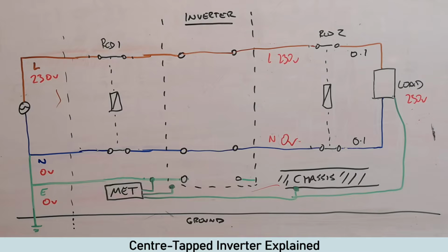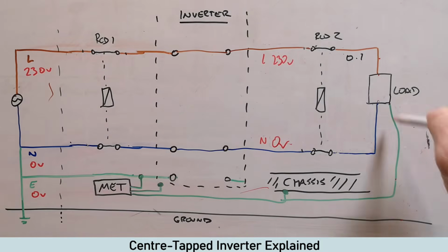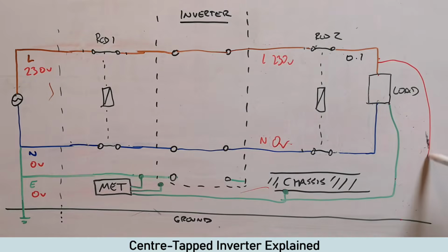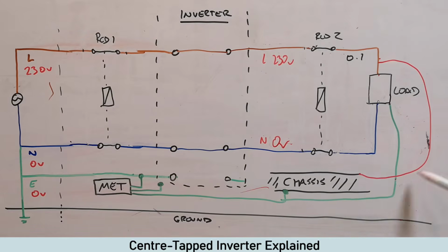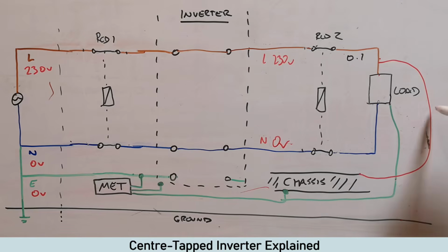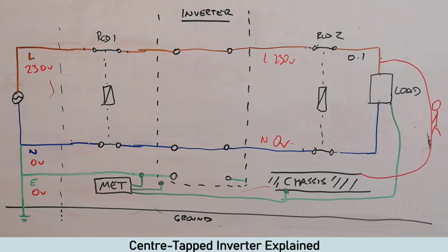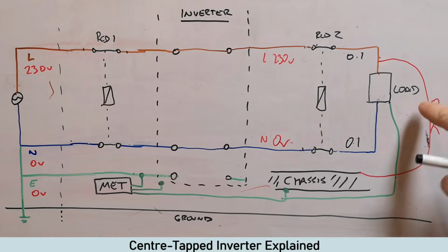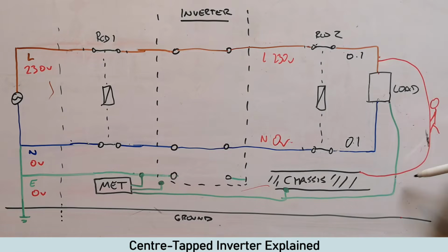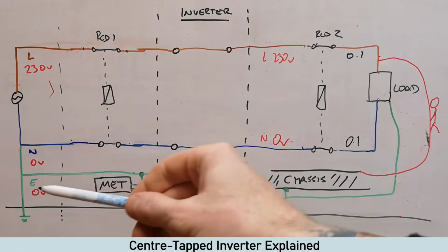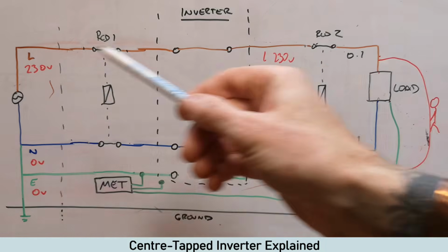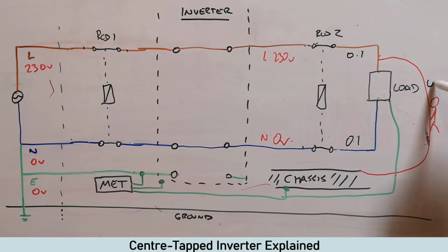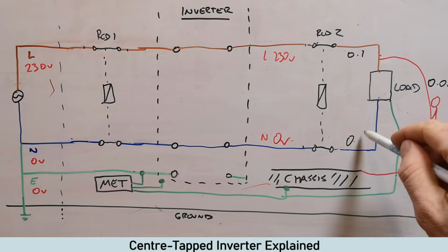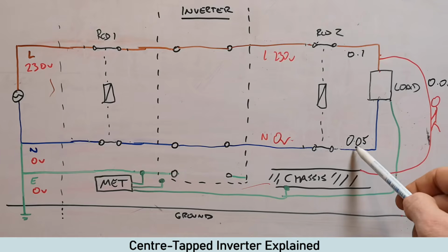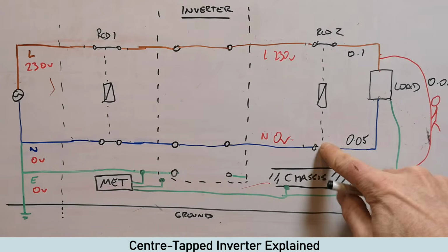Now if there's a fault, you come along and you're touching this live here, and let's just link it. Let's say you stood on the chassis and then you're touching that live there. So this is you touching that. Now again, the RCD wants to see 0.1 coming back in, but because you're touching it, some of that is going to flow through you like we did before, then through the chassis, back through here, through this neutral to earth bond, and back up again. So you're part of the circuit. Let's say 0.05 goes through you, 0.05 goes through there. This is not the same as this, so then again the RCD is going to trip.